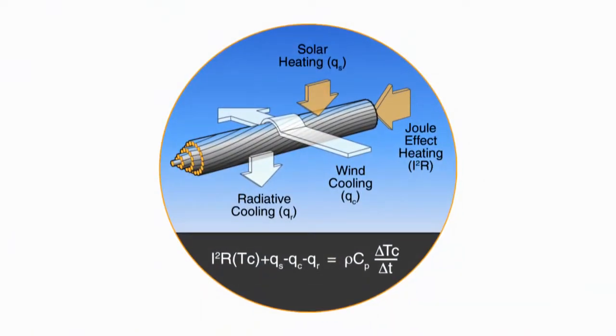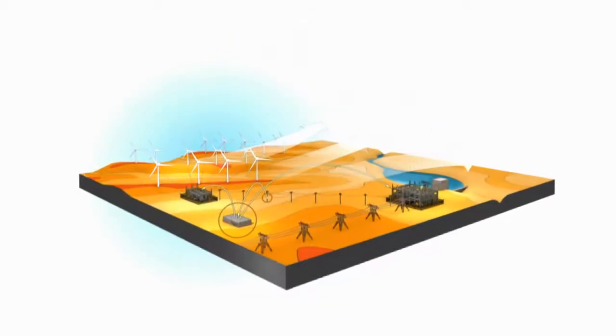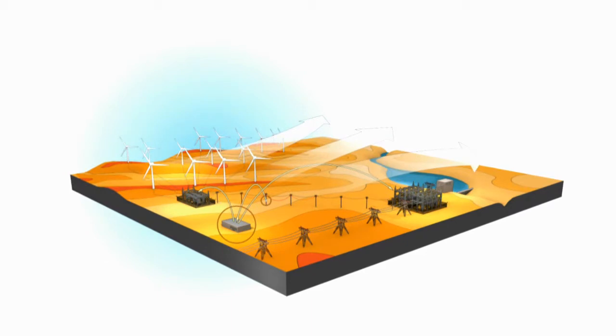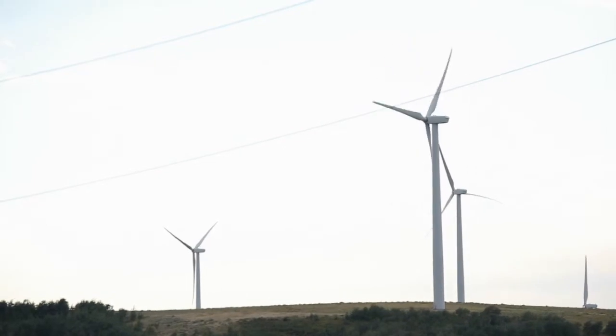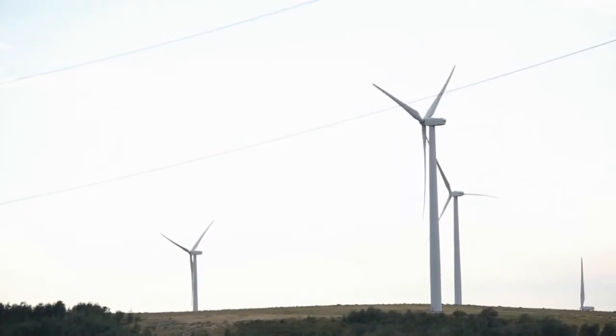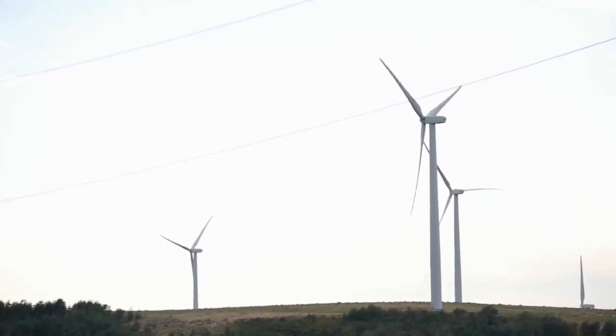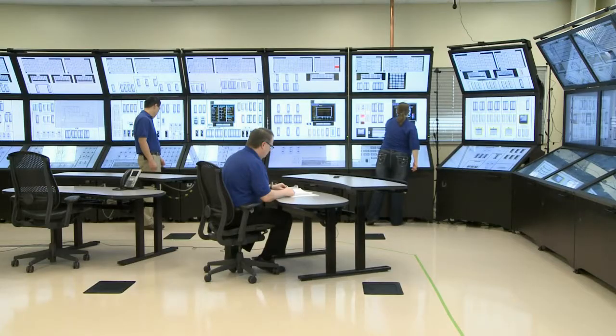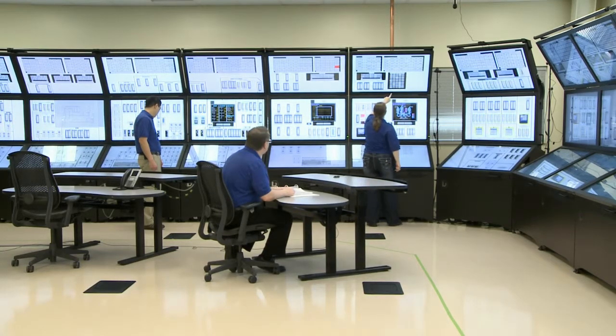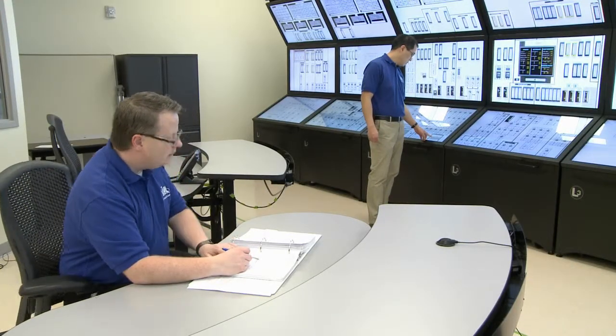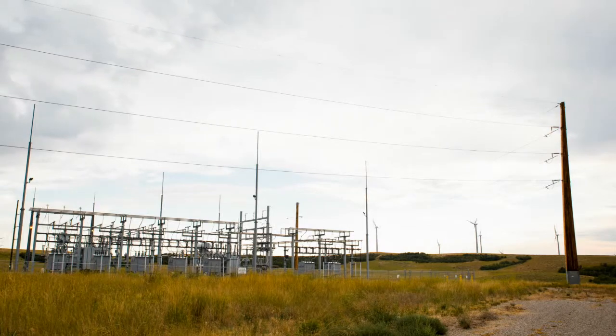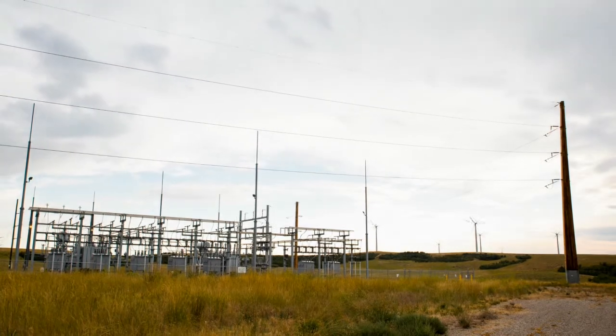Traditionally, the amount of power transmitted through lines is bounded by static limits set with conservative weather assumptions. Yet varying environmental factors can change the amount of cooling on power lines and allow for increased current loads. In fact, lines near wind farms are ideally suited to handle extra electricity generated on windy days. Utility operators could safely maximize the amount of electricity flowing through a grid network if they had access to reliable, real-time information about weather and other conditions along the transmission lines.